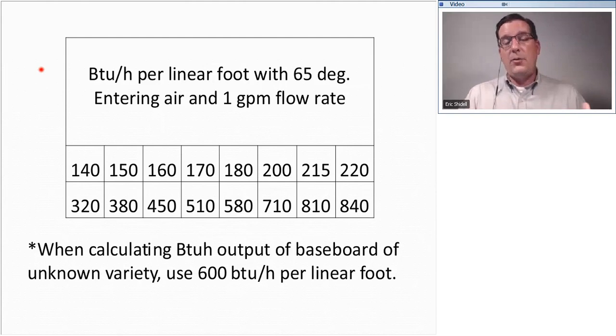The reason may be that there's just not enough baseboard in it. So what you can do is measure the length of the baseboard, look at your water temperature, and if it's 180, then 600 BTU per foot. It may be just that there's not enough baseboard in there and I need to add more. And so this would be one way in order to prove that. Of course, you would then have to do a heat loss calculation on that room and identify, do I have enough baseboard to meet the heat loss or not? And if you don't, now you know. That's how you measure that.